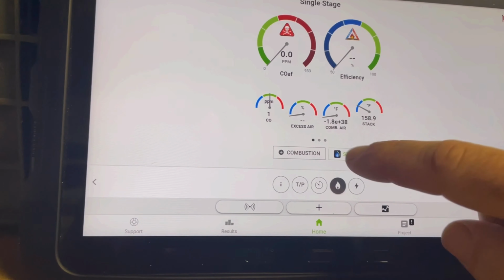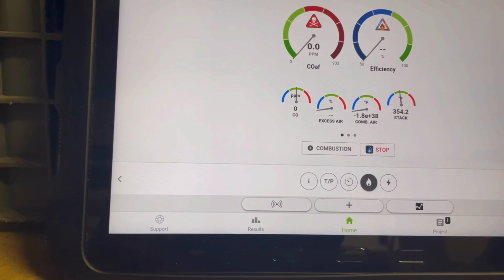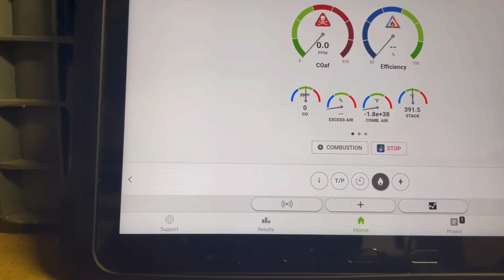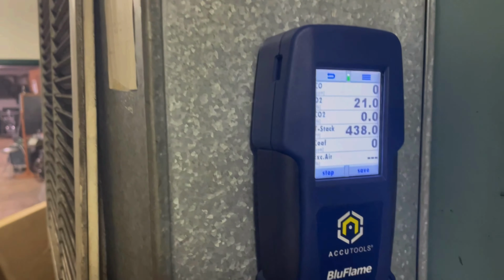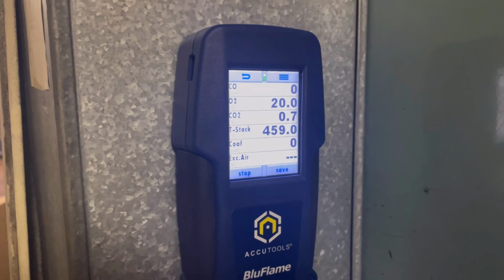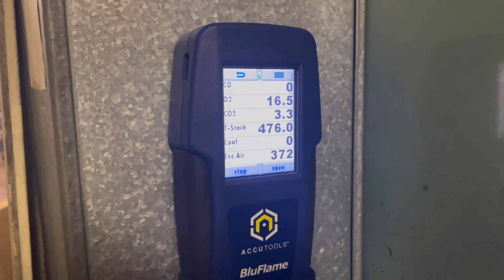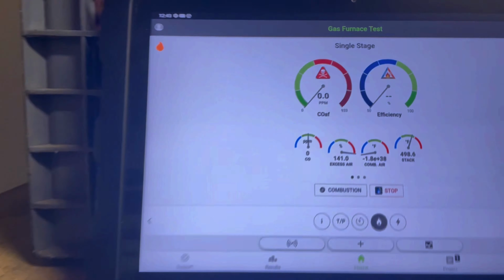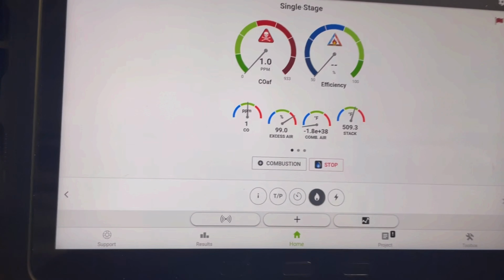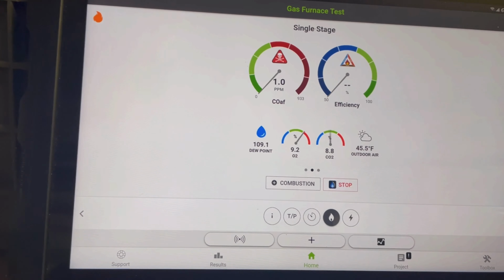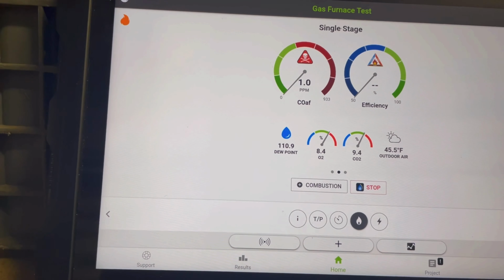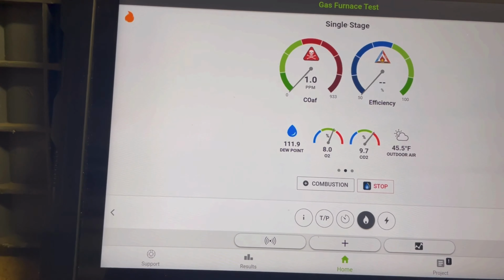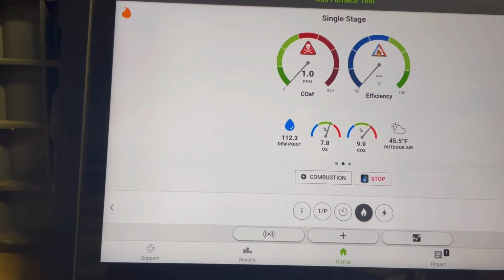Return to my tablet, and I'm going to start the analyzer from the tablet. So now the analyzer is communicating to the tablet. That information is being communicated to MeasureQuick. As you can see, the O2 and CO2 start to come up. I'm having a little issue with the combustion air. Not sure what's going on there, but I'm relatively new to this analyzer, so I'll look into that.